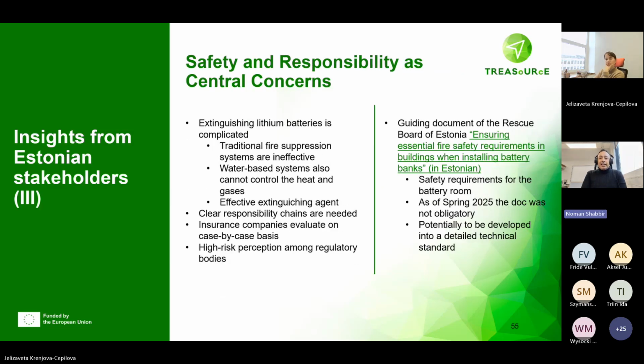As we were saying earlier, safety and responsibility are central concerns. Extinguishing lithium battery fires is quite complicated compared to traditional fire suppression. Ideally, these batteries should be installed in a separate room with a separate ventilation system, not connected to the main ventilation system of the building, because a chemical fire can emit gases that should not go into the main ventilation system. This could increase the cost of the ventilation system for the overall building, and there should also be additional fire suppressing mechanisms in case a battery catches fire.